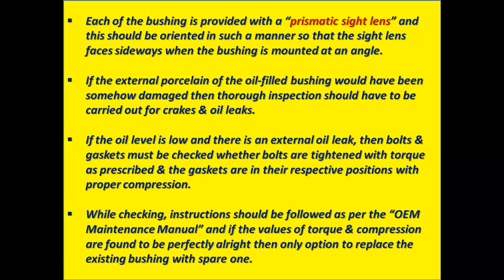If the oil level is low and there is an external oil leak, then bolts and gaskets must be checked, whether the bolts are tightened with a torque wrench to the torque prescribed by the OEM, and the gaskets are in their respective positions with proper compression. While checking, instructions should be followed as per the OEM maintenance manual, and if the values of torque and compression are found to be perfectly all right, then the only option is to replace the existing bushing with a spare one.